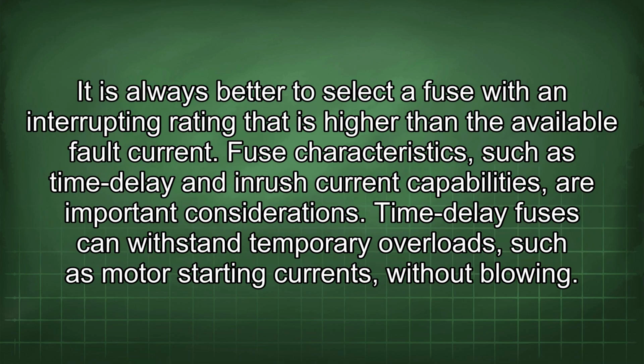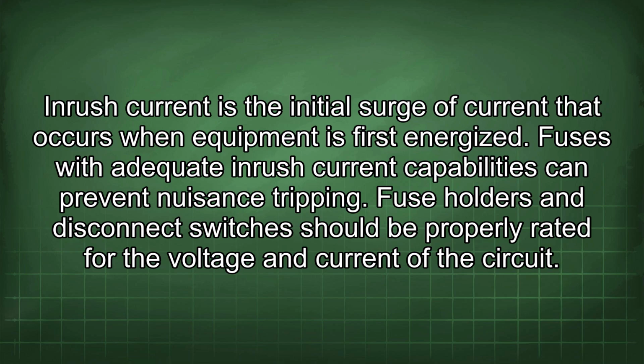It is always better to select a fuse with an interrupting rating that is higher than the available fault current. Fuse characteristics such as time delay and inrush current capabilities are important considerations. Time delay fuses can withstand temporary overloads, such as motor starting currents, without blowing. Inrush current is the initial surge of current that occurs when equipment is first energized. Fuses with adequate inrush current capabilities can prevent nuisance tripping.